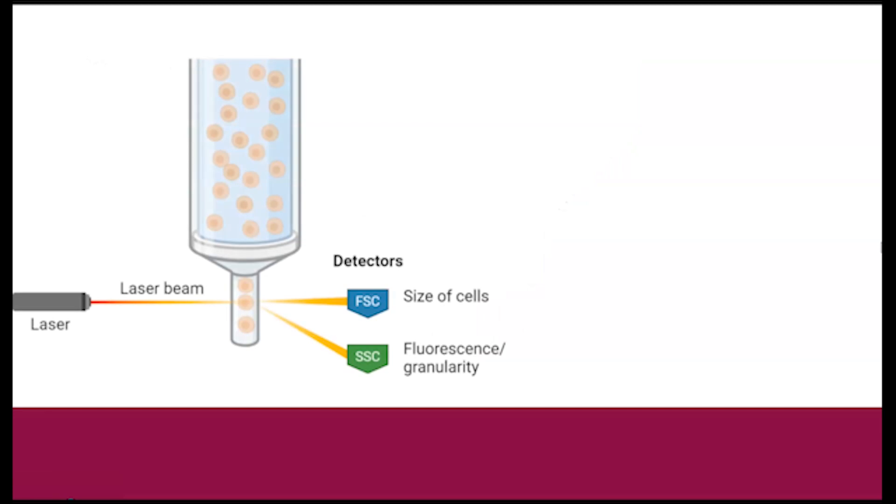Within the second component, or the optical system, the focusing of the sample of cells in a single file streamline leads into the second part of the technique, in which a laser will strike each cell at the interrogation point. As the light strikes, light scattering occurs in two main ways: forward scatter and side scatter. In forward scatter, the larger the size of the cell, the greater the forward scatter, meaning the angle is greater as the light reaches the detector.